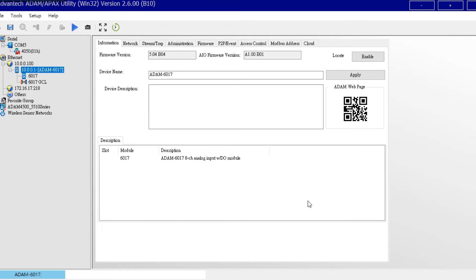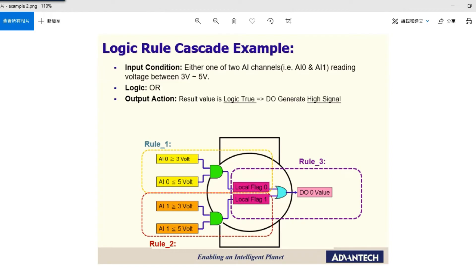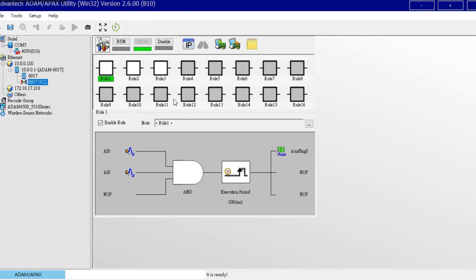After finishing the first example, let's see the second one — logic rule cascade. Here we use Adam 6017 for testing. We want to achieve the following function: in the Adam 6017, if either one of two AI channels — AI0 or AI1 — raises the voltage within the range of 3V to 5V, then DO0 will be triggered into logic high. Here is the GCL rule to set in the utility. Both rules are set in the local input module, which is Adam 6017.